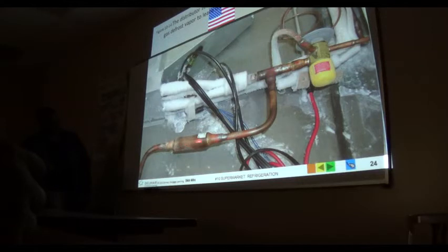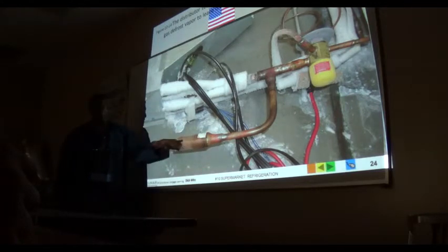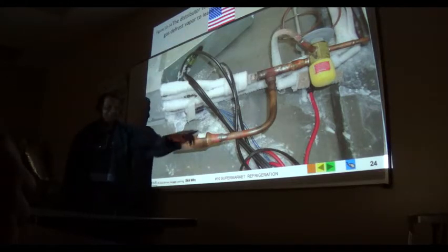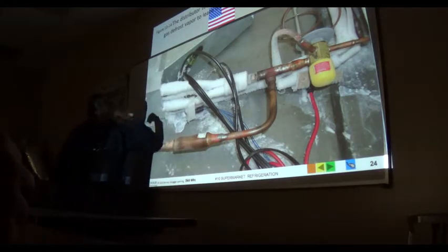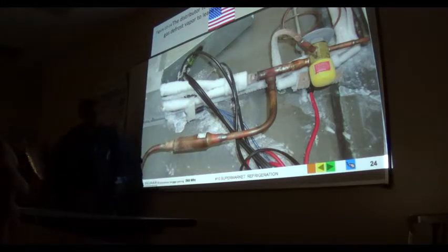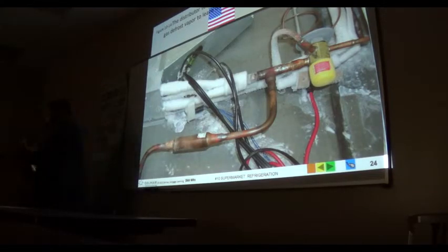Where's the check valve? Is there a check valve on there? Over here, this one here? That's a check valve. Looks simple, right? It looks like a filter dryer. Remember some time ago I told you guys it looks exactly like one of those copper-style filter dryers. But it does say check, and you can hear the ball inside here. It'll have an arrow on it or something, right? Yes, because it is sensitive to flow. This one is directional, so it will have the arrow.